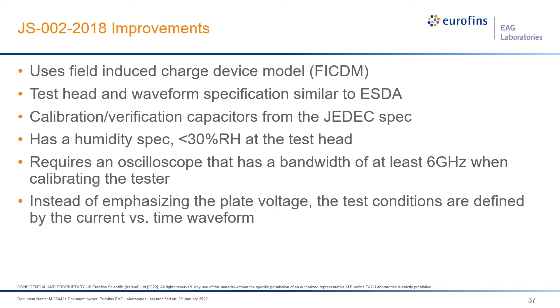One of the new requirements: you have to use an oscilloscope with a bandwidth of at least 6 gigahertz when you're calibrating the tester. You're still allowed to use the 1 gigahertz scope when you're doing the daily checks, but we don't do that. EAG is standardized on 8 gigahertz oscilloscopes in all of our labs for doing both the calibration and the daily checks. And finally, instead of emphasizing the plate voltage to define CDM, it's defined by the current versus time waveform that you see on the calibration/verification capacitors.